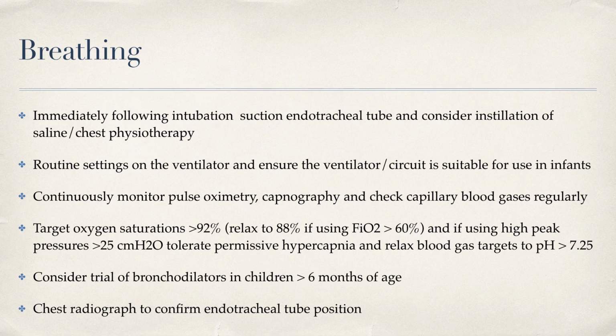Going on to setting up the ventilator, it's pretty much standard settings like I've described before. So I would use an I:E ratio of 1 to 2. From a PEEP point of view, most of these kids start in about 5 or 6 centimetres of water. If the chest x-ray shows significant collapse consolidation and I'm trying to open that up, probably starting about 8 centimetres of water. If then the child is needing significant amounts of oxygen to maintain saturations, then I would titrate the PEEP up in relation to that. So if they're on 6, going to 8, if they're on 8, going to 10, and just titrating that to the oxygen that they need.